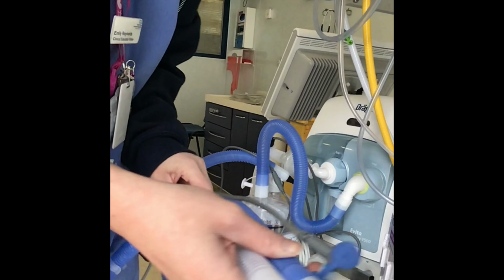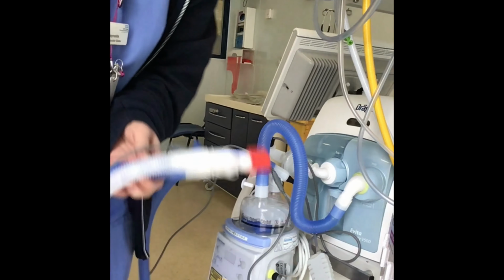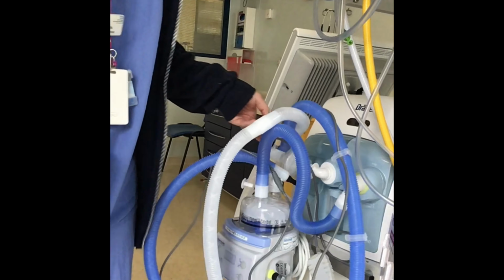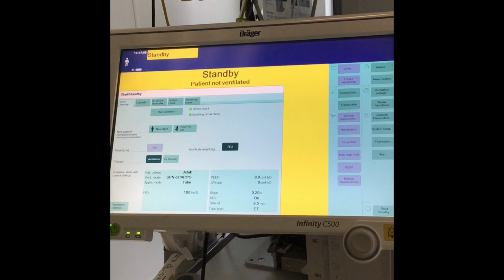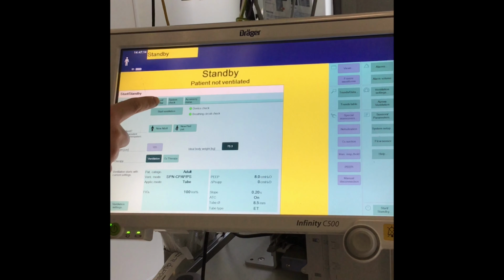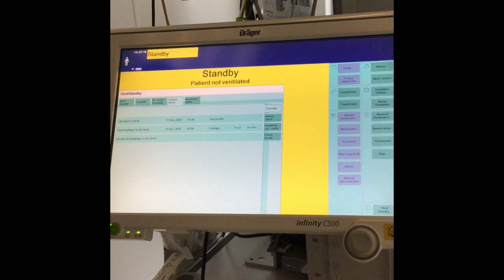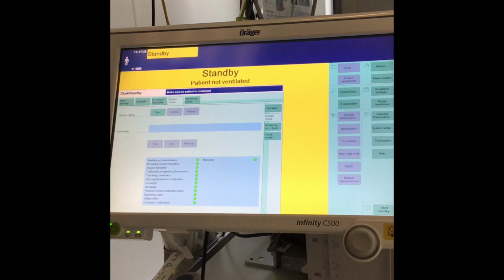At this point you're then ready to put the tubing through its checks. So you're now going to put the ventilator through its checks. To do that, you've got some headings here, one of them being system checks, so you're going to hit that. And then you've got some more tabs down this side. So first of all we're going to put the actual ventilator through its checks, so this would be device check.